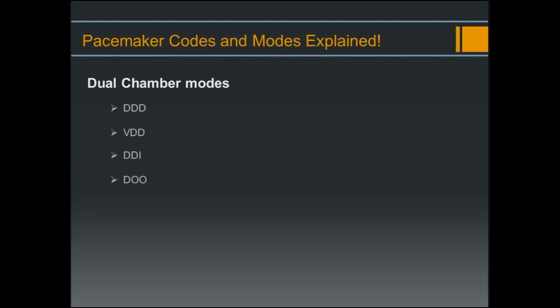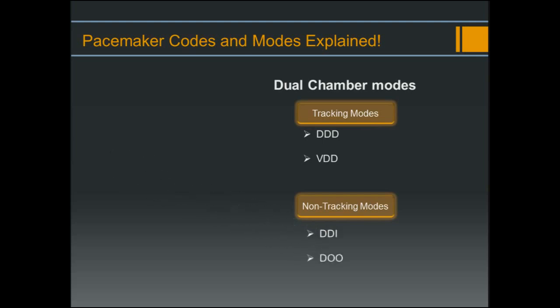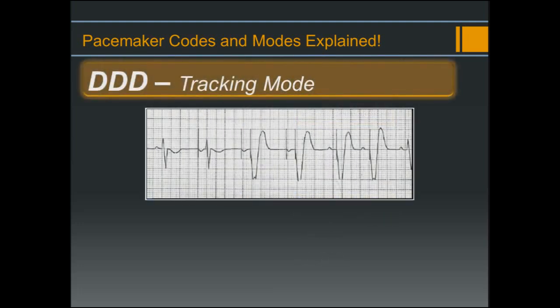The dual chamber modes are DDD, VDD, DDI, and DOO. It's easier to break dual chamber modes into two categories: tracking modes and non-tracking modes. The tracking modes are DDD and VDD, and the non-tracking modes are DDI and DOO. First up is DDD tracking mode.